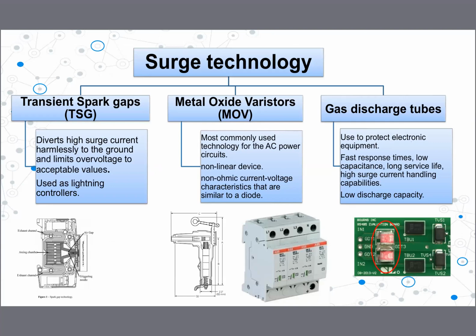I told you we need a surge protection device to bring down the voltage level to a non-hazardous level in the electrical system, right? And I explained that the hazardous voltage level in the electrical system is not constant throughout, right? So it changes from one place to another. So surge protection technology is also different. There are different technologies we use, and therefore we have different types of surge protection devices, and we need to know what technology of surge protection device we need for this particular place in the electrical installation, right? So that is part of the selection of surge protection devices. Before that, we need to know what the technologies are, right?